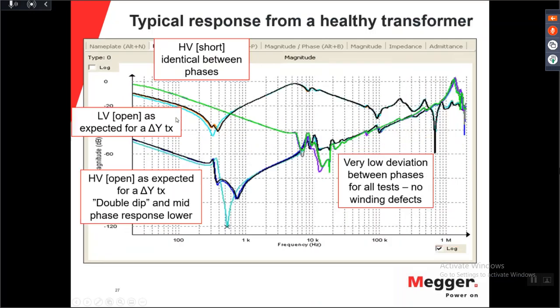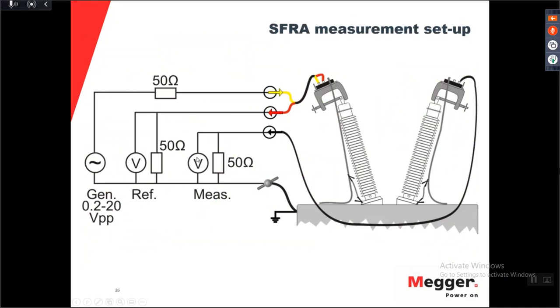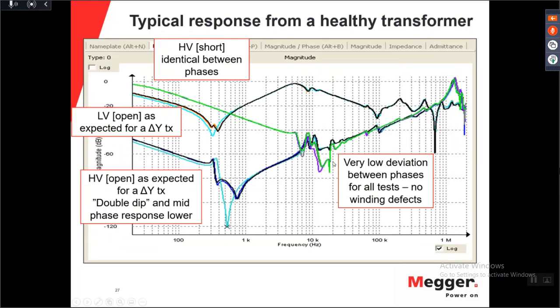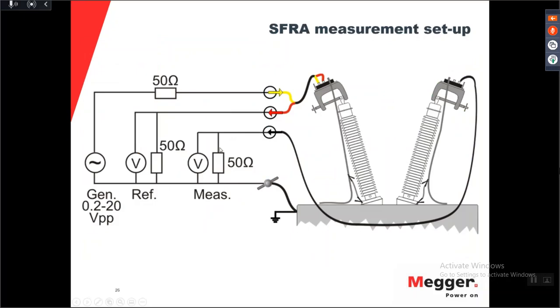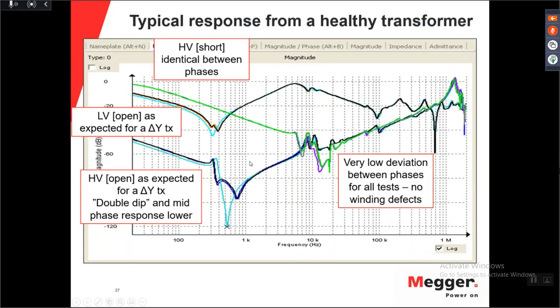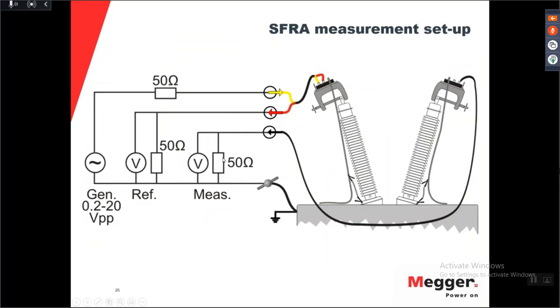The instrument dynamic range is how good this voltmeter is. If you have a voltmeter capable of measuring 1 nanovolt, you will be able to measure a much larger attenuation without any signal noise. But if your voltmeter is only capable of measuring millivolts, your capability of measuring a transformer will be affected here. So your noise floor will be set here. So you have millivolt, microvolt, nanovolt, which is basically how accurate, or how noisy, your voltmeter is. That is very often specified for each particular brand of SFRA equipment.